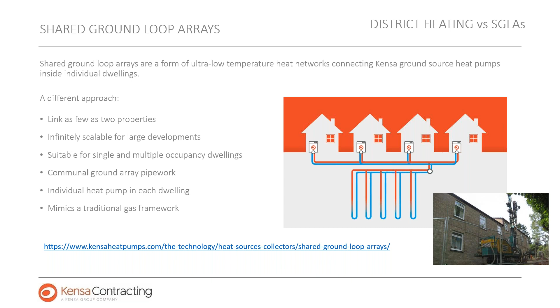So the benefits of a shared ground loop array, where we connect up multiple boreholes and share them across multiple properties: it's an ambient temperature distribution. Remember that temperature coming from the ground is typically 10 to 12 degrees centigrade. So there is no chance of any district heat losses or overheating in the riser pipework that will feed multiple properties. There's potential for free summer cooling as well. That depends on the type of emitter used within each property. For example, fan coils can offer cooling.